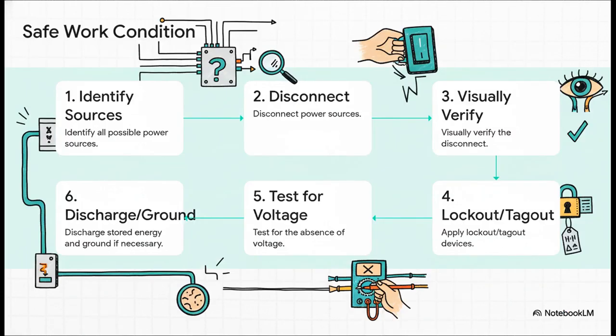Turning power off is a lot more involved than just flipping a switch. NFPA 70E lays out a specific six-step process to create what's called an electrically safe work condition. You have to find every power source, disconnect them, visually confirm they're disconnected, put on locks and tags so nobody can accidentally turn it back on, and then test it to prove there's zero voltage. You have to do all of that before it's actually considered safe.